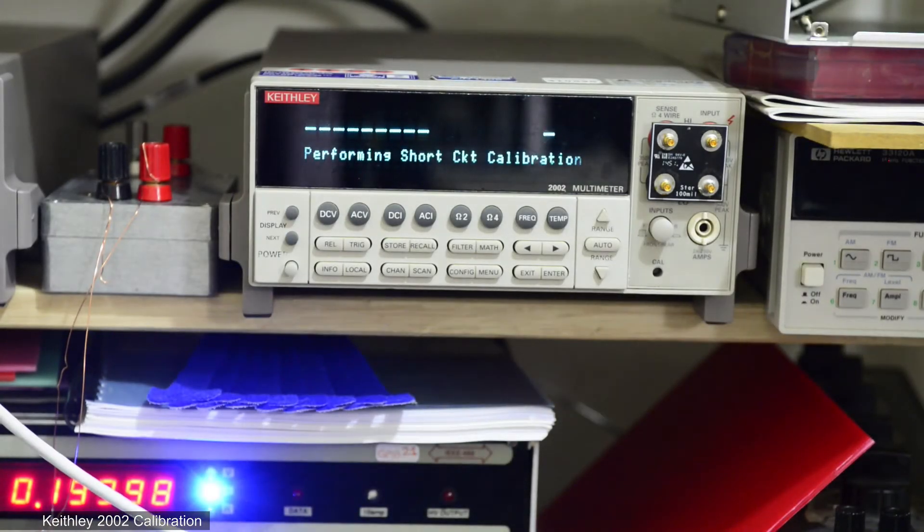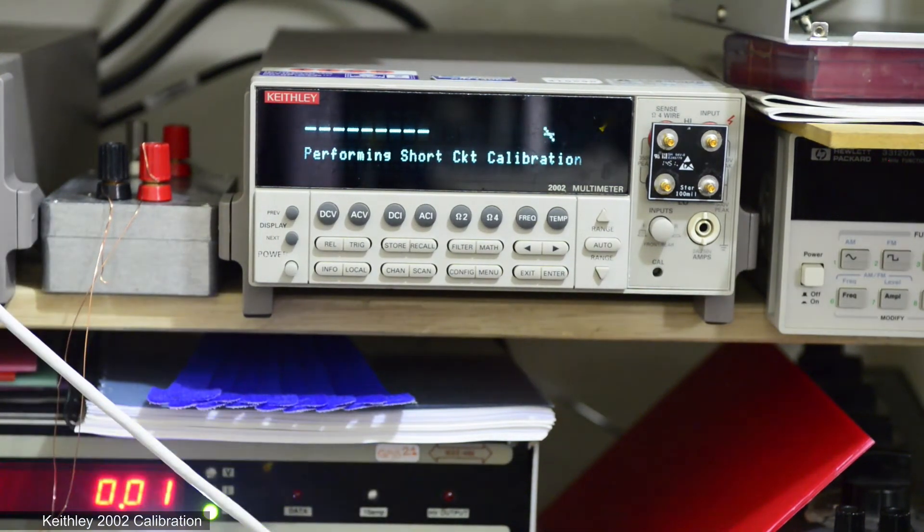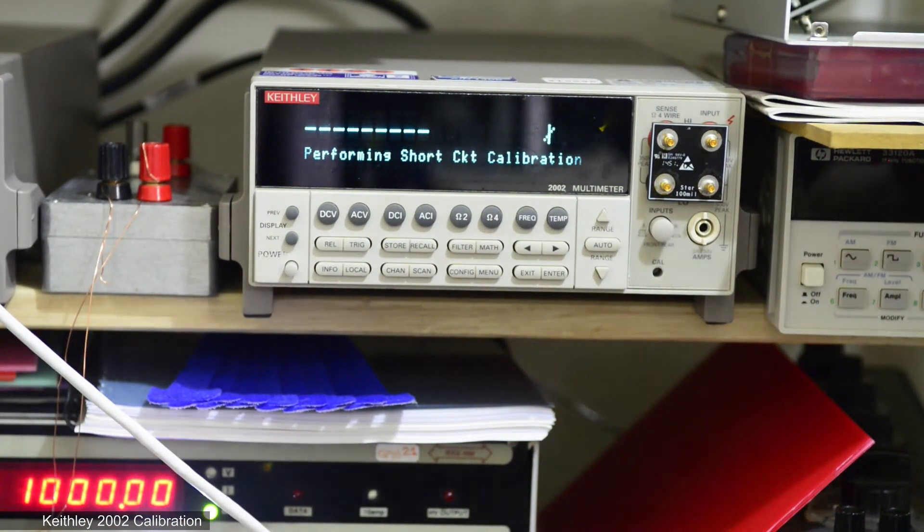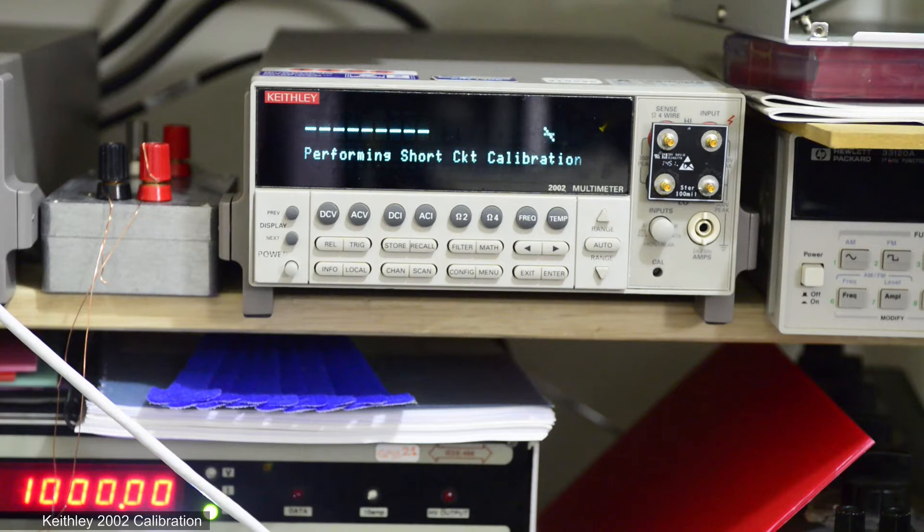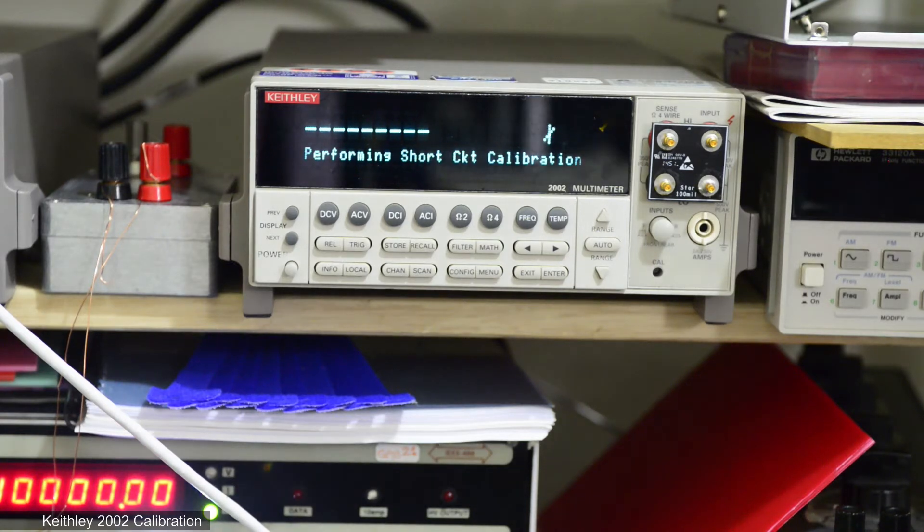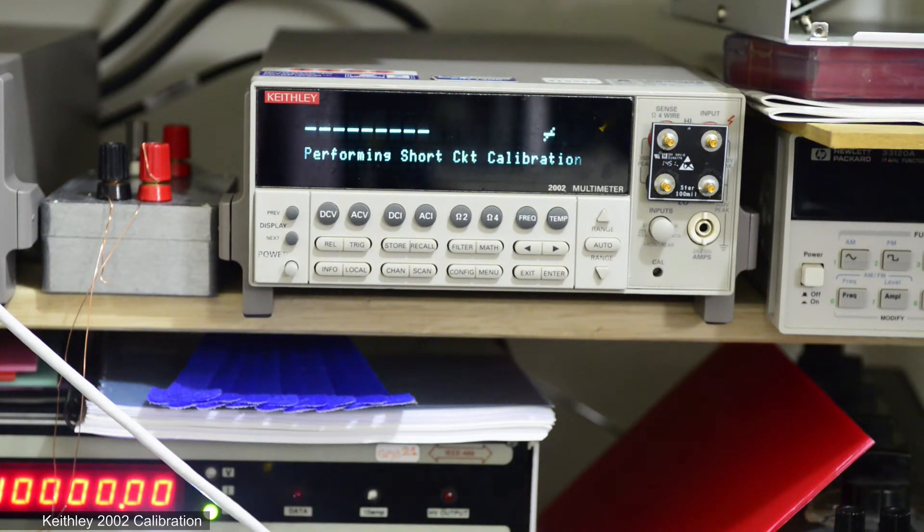I use my own 4 terminal shorting plug for short circuit calibration. This step takes about 5 minutes so video is sped up.